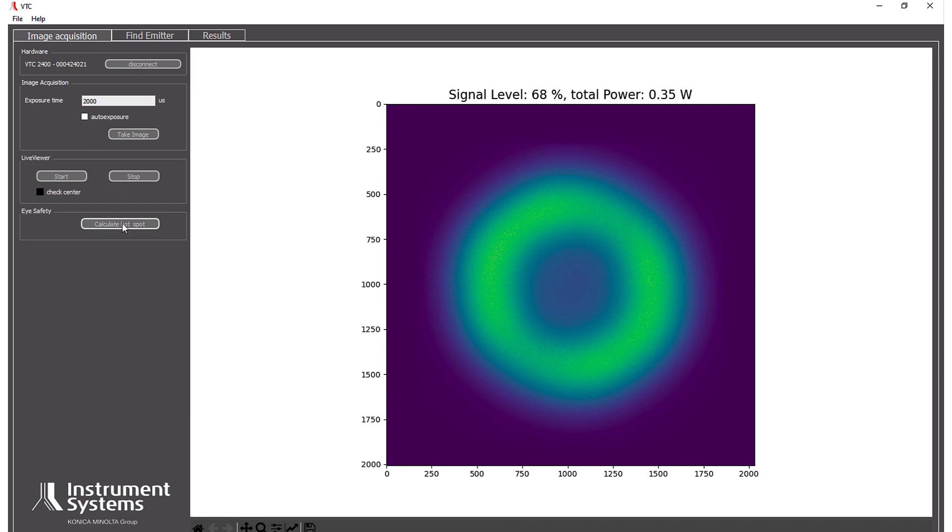We have to know on which position we have the hotspot of the beam. So then we can just press calculate hotspot. And then it will calculate the position where the beam has its highest intensity in a 7mm spot in a distance of 10cm as defined in the laser eye safety standard.